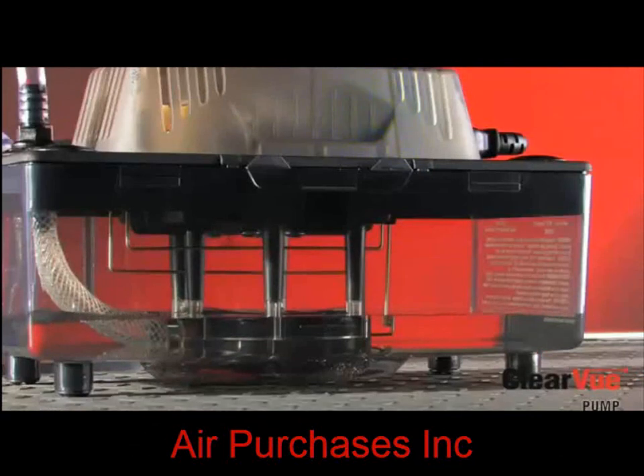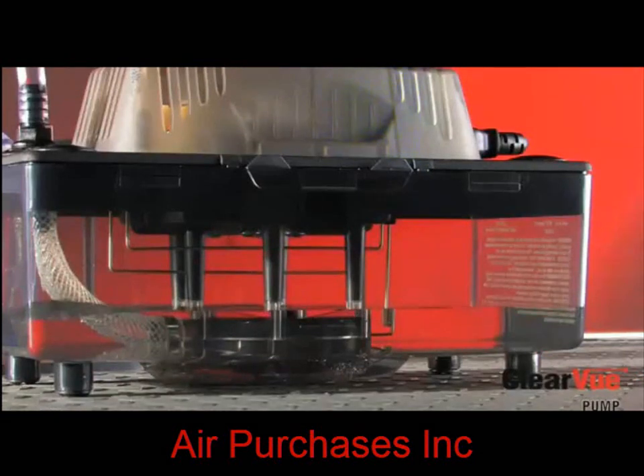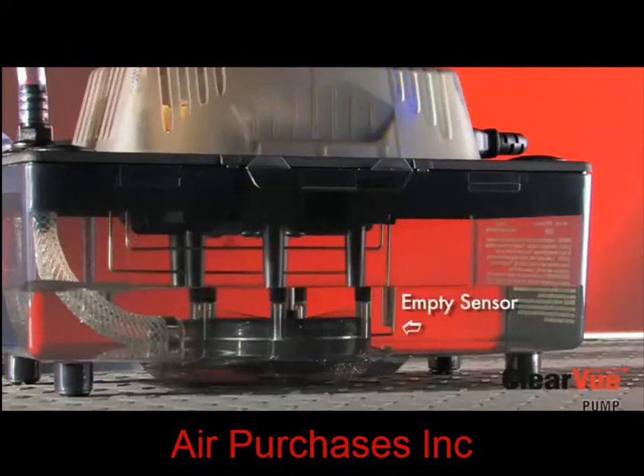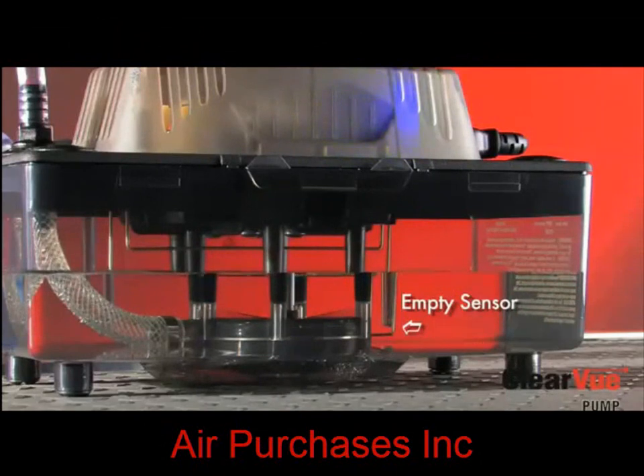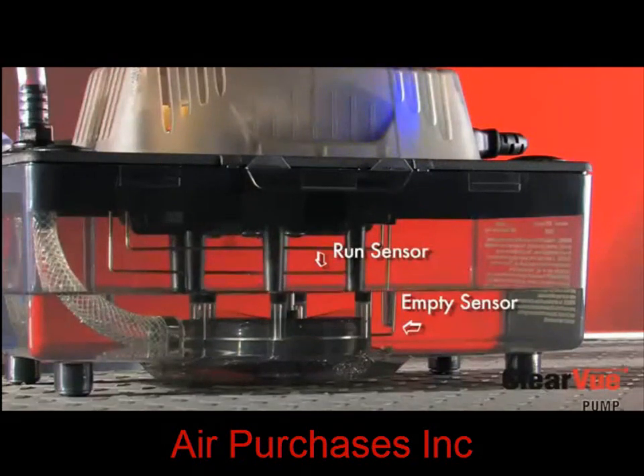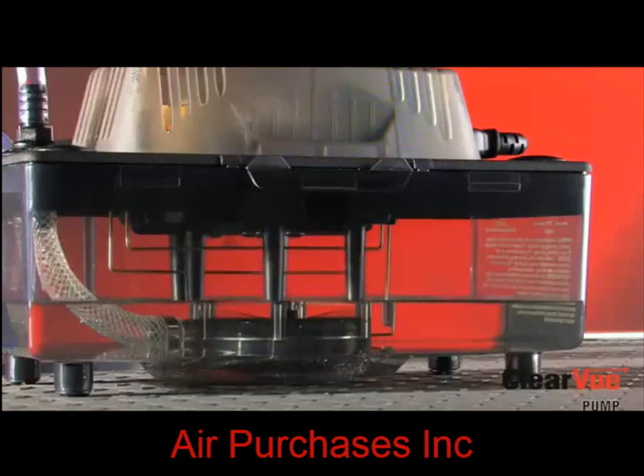As you can see, water is coming into the tank and it's touching that empty sensor, the bottom sensor. This sensor lets ClearVue know that there's water in the tank. Water will continue to rise until it touches the run sensor. The run sensor uses what we call our IQ technology, which are the brains behind the pump. These brains determine how fast to run the motor to remove the condensate.